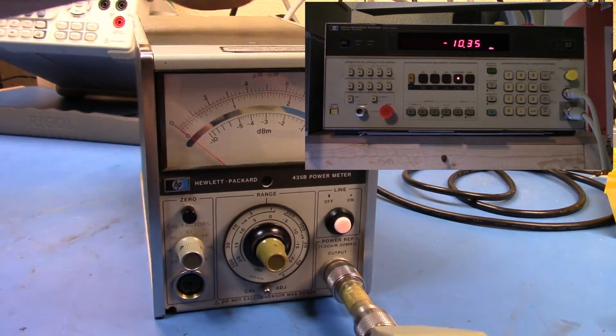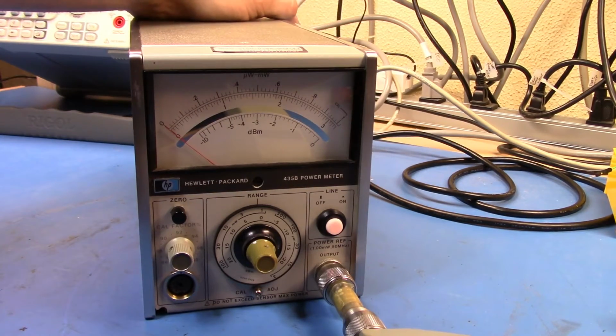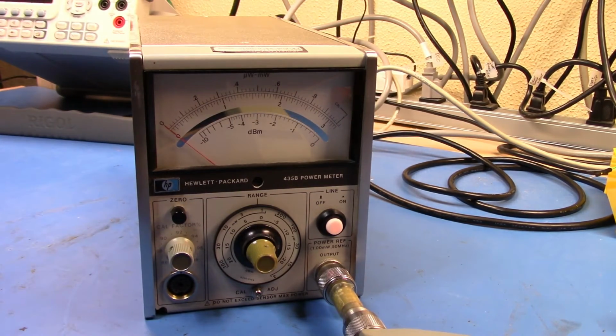So let's turn the power reference off. Actually, I don't even need to unplug it because I can leave that on, turn the power reference back on, and push the button up here to go to frequency, and you would have heard the little click. If I look at the frequency, it is 49.8694 megahertz, which is well within spec. It's 50 megahertz plus or minus 5 megahertz in terms of the frequency output.